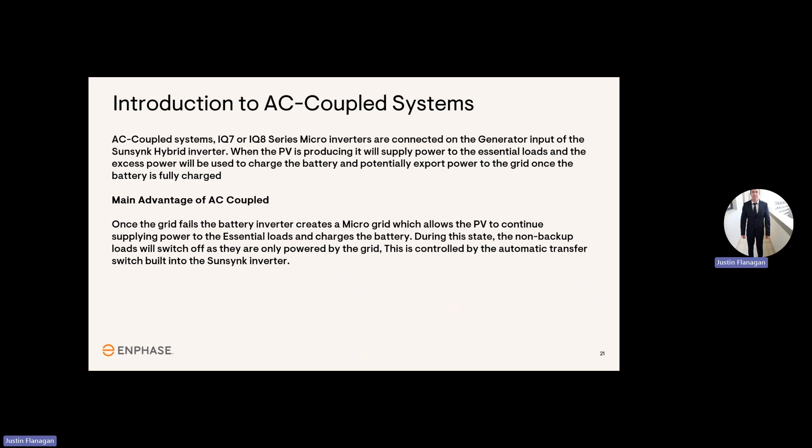The main advantage of AC-coupled, once the grid fails, the battery inverter creates a microgrid, which allows the PV to continue supplying power to the essential loads and charges the battery. During this state, the non-backup loads will switch off as they are only powered from the grid. This is controlled by the automatic transfer switch built into the Sunsynk inverter.